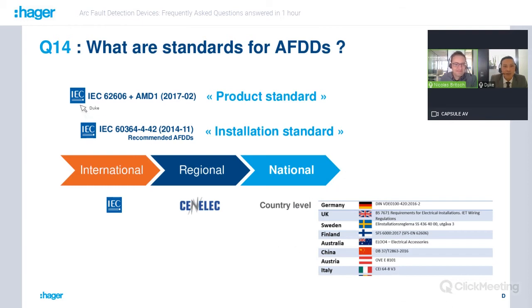But very quickly, as already mentioned, the product standard is IEC 62606, plus the amendment in 2017. We have the installation standard, IEC 60364-4-42, which recommends AFDDs, so for your information. So we have here the three levels: international, regional, national, and we come to country levels. That's important to understand as well in your countries. The national standards recommend, follow, or are similar to the regional or international ones, which recommend AFDDs. So examples: Germany with the DIN and VDE, the UK with the BS standard, and Sweden with the SS standard. Some examples to see that AFDDs are recommended in these standards.